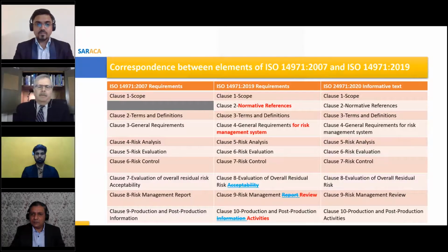The other thing that I wanted to mention was, again, the design inputs need to include the applicable outputs of risk management, which are risk control measures that are defined in ISO 14971, but are also defined in 13485:2016. So that implies that you need to do your risk analysis before your design input. And again, that needs to include more risk tools and techniques than just the FMEA.